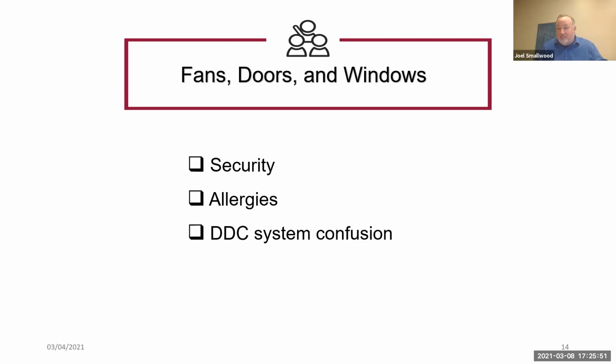to go out to a problem that's not necessarily a problem. If we see that cold room on our computer system, we might assume there's something wrong in the room. When we get out there, there's a window open. Or like you say, if a system is ramped way up and running at high speed, we can't tell why from here. We unfortunately can't monitor the windows from here. So we end up sending someone out to look at it to try to figure out why the system is doing what it's doing, because it won't tell us everything for sure.